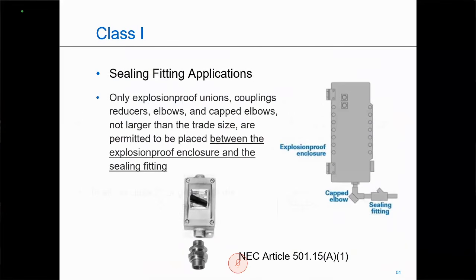Now, this is one that we started to allude to a little bit earlier with the question. And here is where the National Electrical Code tells me that I may put certain explosion-proof or rated fittings between the explosion-proof enclosure and the sealing fitting. My 18-inch rule still does apply. And up until 2017, the code also used to say T's and L's, but that was actually eliminated in 2017. Now it's unions, couplings, reducers, elbows, capped elbows, not larger than the trade size.